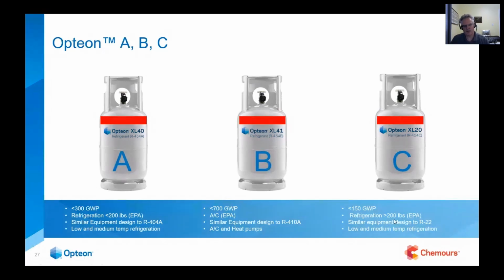But I know some people have already asked me, is A for medium temp and C for low? It's like, no, they both have similar boiling points. They can both do medium and low temp refrigeration. It's really going to come down to what the GWP requirement is and what the manufacturers have migrated to. And then when we look at XL41 or 454B as the primary alternative for replacement of 410A in air conditioning equipment, it has properties similar to 410A, and will be used quite a bit in the air conditioning and heat pump markets.